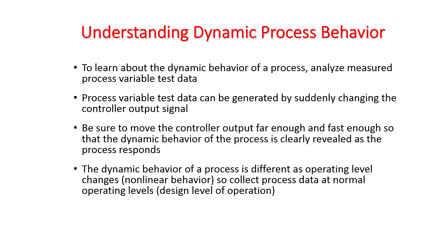One way to generate that data is to make a step change — suddenly change the input to the system, or what we call the controller output. The controller output becomes the input to the system. We need to make sure we move the controller output far enough and fast enough so that we can see this dynamic behavior. We'll also be looking at understanding the nonlinear behavior of these processes.